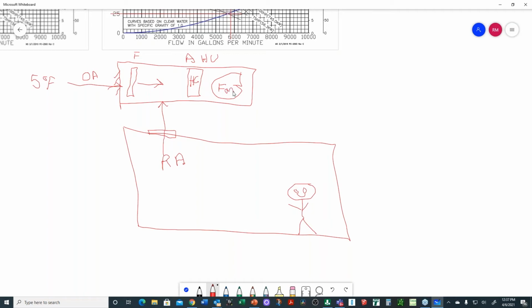Then we have some more ductwork, and that ductwork finds its way into the room here. And then that becomes the supply air. So we call this the supply air here, SA, supply air. That's not the best S in the world, but we have our supply air, which comes into the room from the air handling unit. The return air mixes with the outside air, passes over the heating coil, and gets blown through the ductwork into the room itself. So hopefully that answered that question.